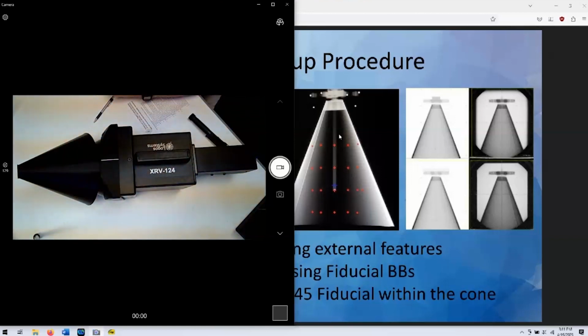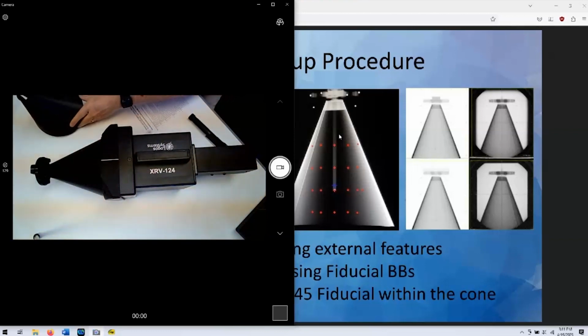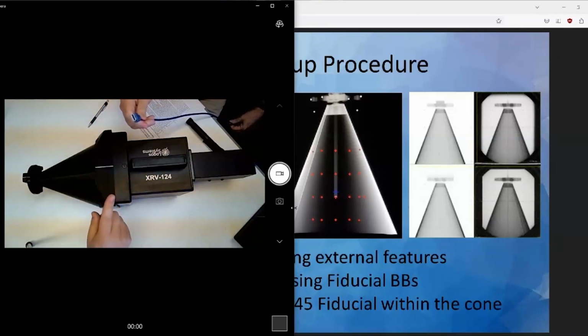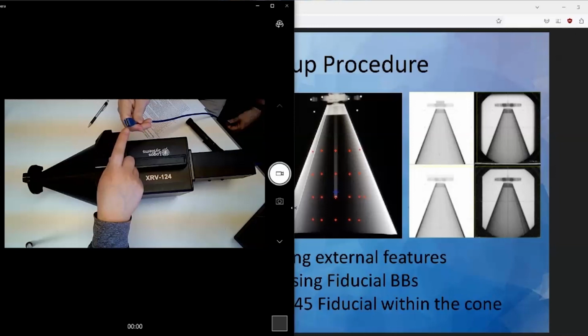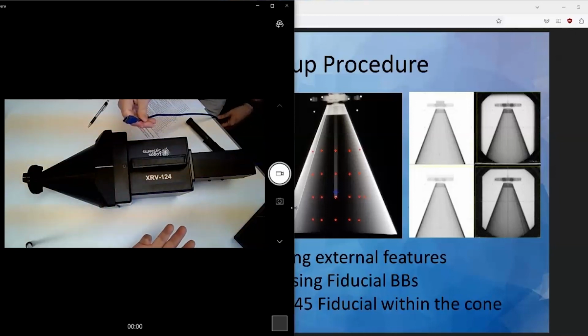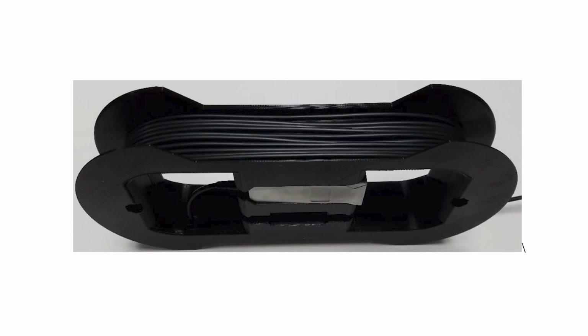If the BB fiducials are always being used for image alignment during star shot capture, then it's recommended to keep the shroud mounted. The 30-meter USB 3 extender cable supplied with the XRV-124 is called power-over-fiber-optic because the laptop powers the digital camera through power wires in the cable. High bandwidth signals are converted to light at the laptop end of the cable and converted back to electricity at the XRV-124 end of the cable. The cable does not support USB 2 signal communication.